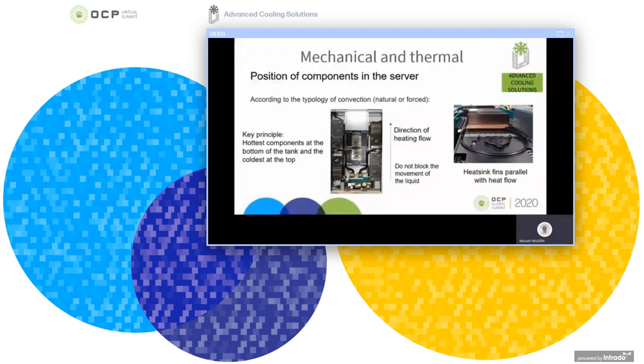Regarding the servers themselves in immersion, the position of the components in an immersed server is directly related to the heat flow. Overall, to optimize cooling, the hottest component will be placed at the bottom of the server, and the coldest will be placed at the top of the server. However, if the technical specifications of the servers do not allow this typical location, a thermal study combined to a test will be carried out to find the right cooling.